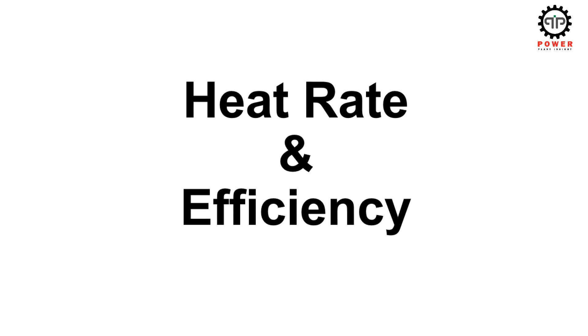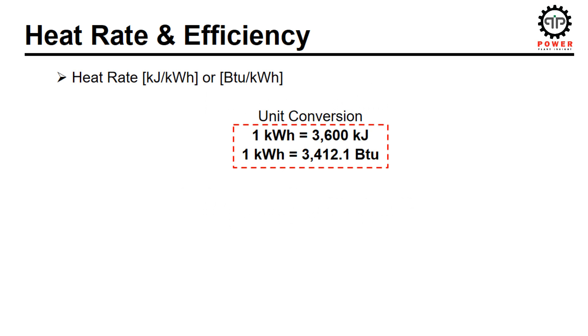Heat rate and efficiency: once we have the value of heat rate, it can easily be converted to efficiency numbers. The concept of heat rate and efficiency is simply a conversion of engineering units — this is a term that power plant colleagues usually misinterpret. Units of heat rate are normally in the form of kJ per kWh, or it can also be in BTU per kWh depending upon the system followed. For conversion of heat rate to efficiency, we need to remember the unit conversion of kWh to kJ or BTUs.